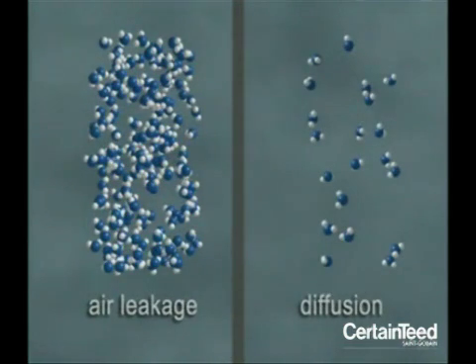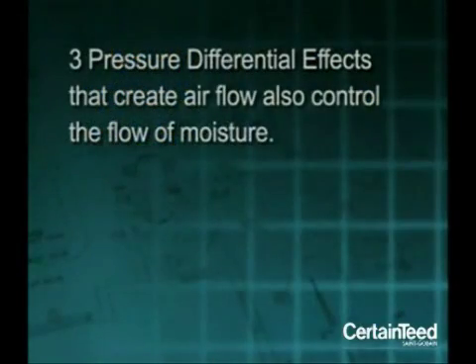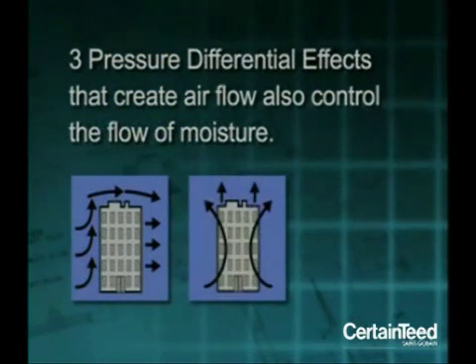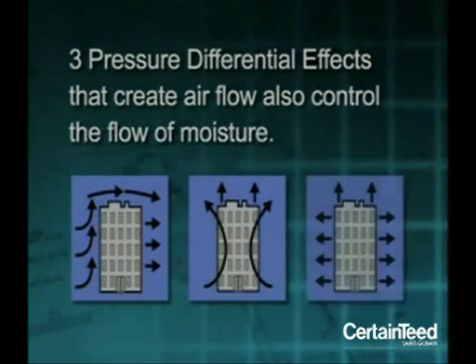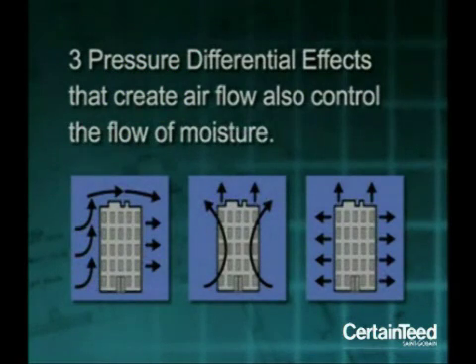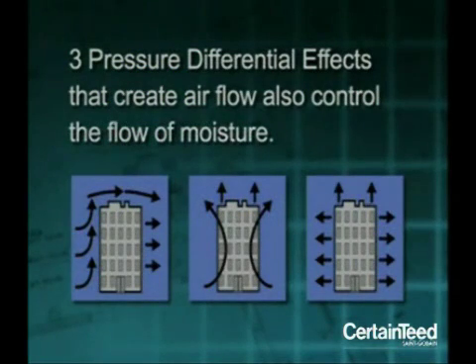Because moisture is carried in air, the three pressure differential effects that create air flow — the wind effect, the stack effect, and the mechanical effect — also control the flow of moisture. If the building is air sealed, less moisture will be released to the outside.